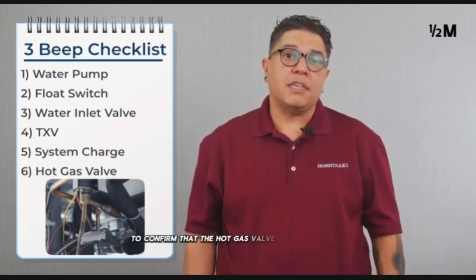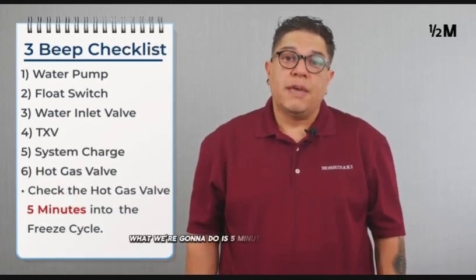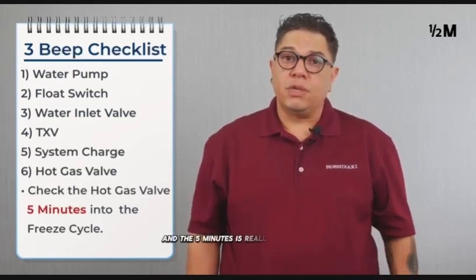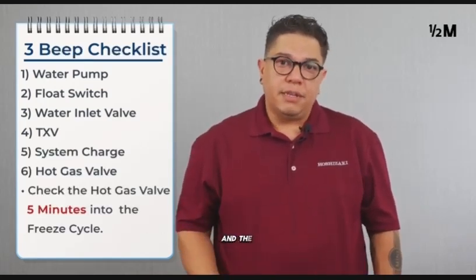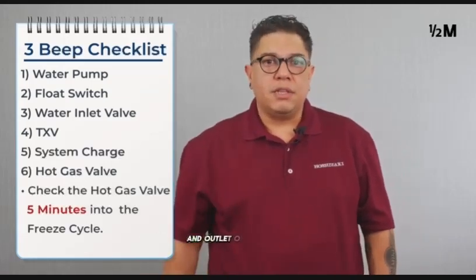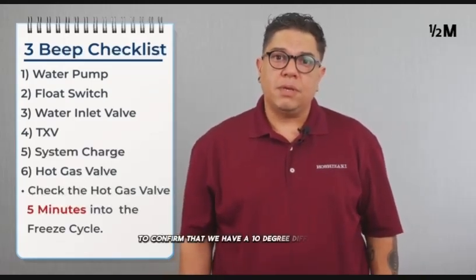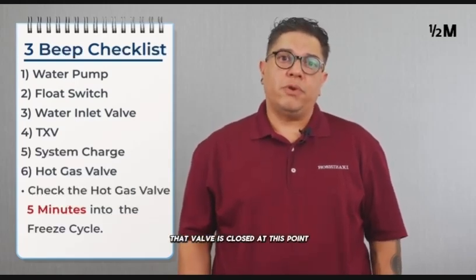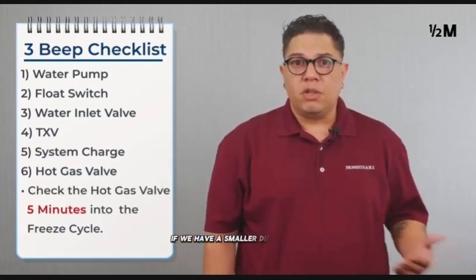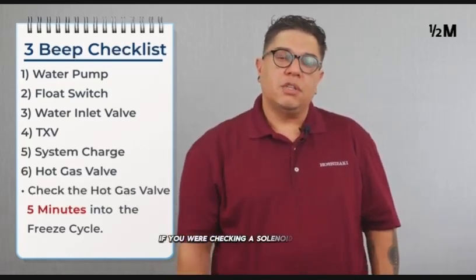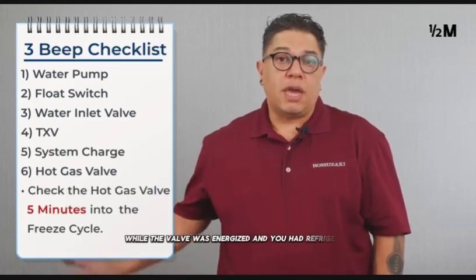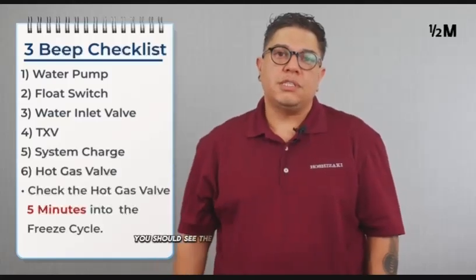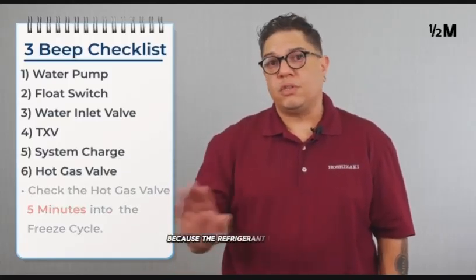To confirm that the hot gas valve is not leaking by, what we're going to do is 5 minutes into the freeze cycle. The 5 minutes is really important because in the 5 minutes prior to that, the hot gas valve was energized. We want 5 minutes to cool down on that valve, and then we're going to take a temperature on the inlet and outlet of that valve to confirm that we have a 10-degree differential. That valve is closed at this point. That's what we're looking for. If we have a smaller differential, the valve is leaking by. The science behind that is if you were checking a solenoid valve while the valve was energized and you had refrigerant flowing through the valve, you should see the same temperature on both sides because the refrigerant is flowing.